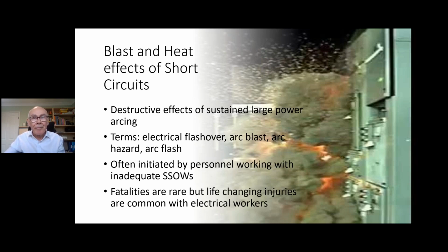Arc flash is often initiated by electrical personnel working to inadequate safe systems of work - in other words, perhaps working live on equipment when they shouldn't be. There's no reason for them to work live, and it's a perennial issue in industry, where safe systems of work need to be written in such a way as to not only discourage live working but to control it, making sure it doesn't happen where it doesn't need to.